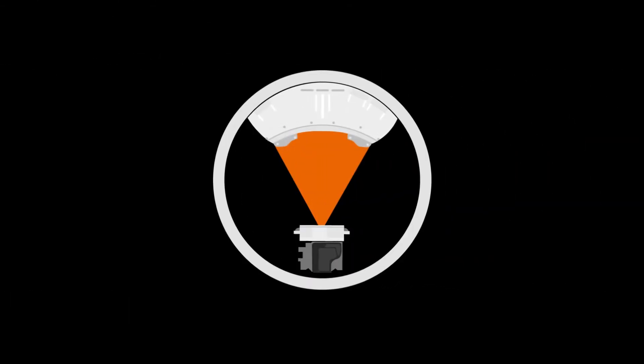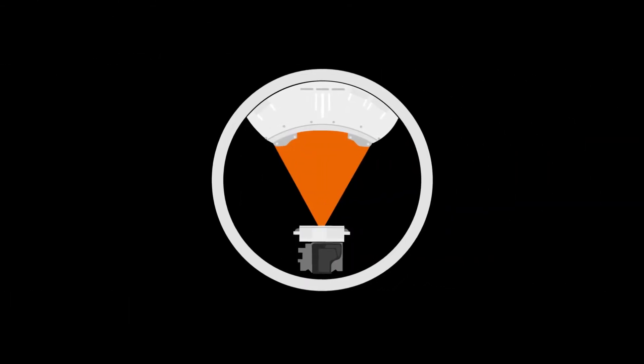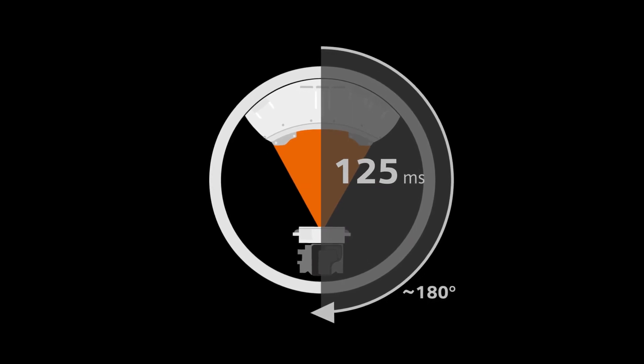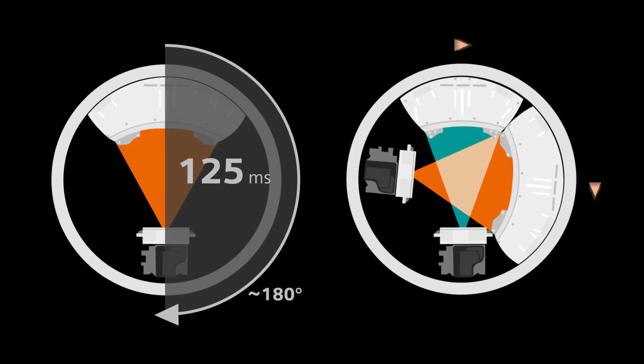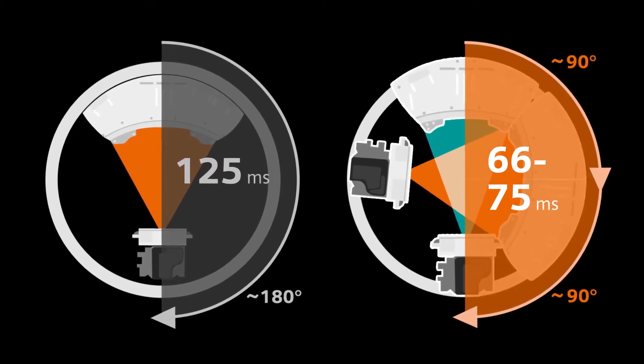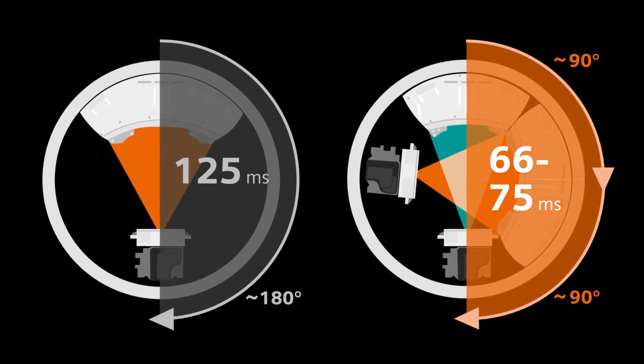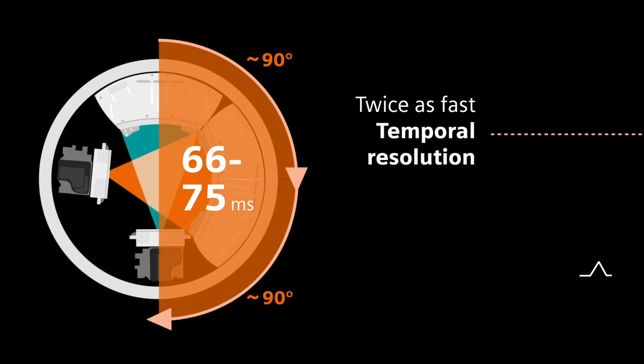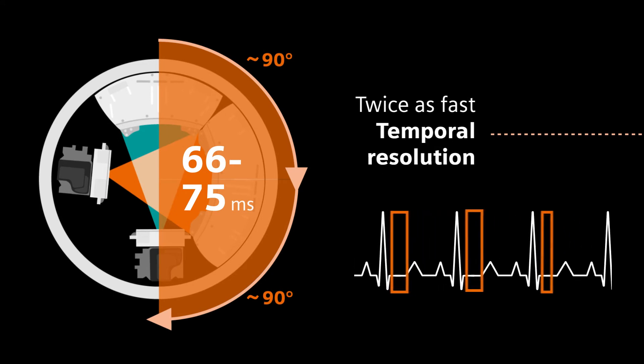While a conventional single-source CT scanner needs to rotate at least 180 degrees to acquire an image, a dual-source CT scanner needs to travel just 90 degrees because it uses two X-ray sources and two detectors simultaneously. As a result, dual-source CT offers faster temporal resolution compared to conventional single-source CT. In fact, it is twice as fast.